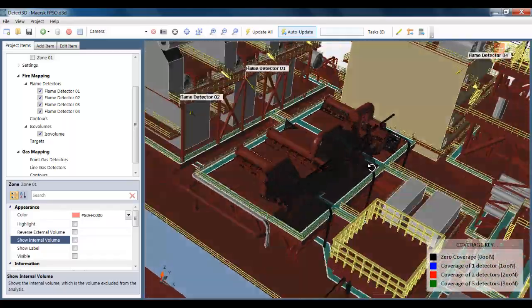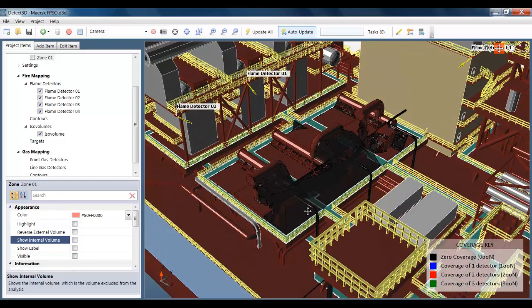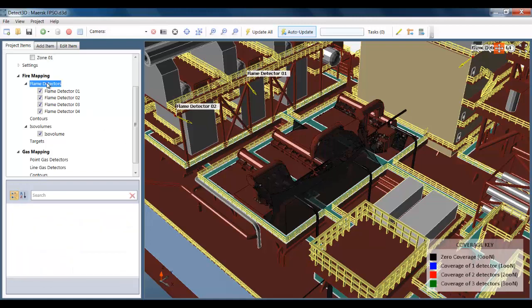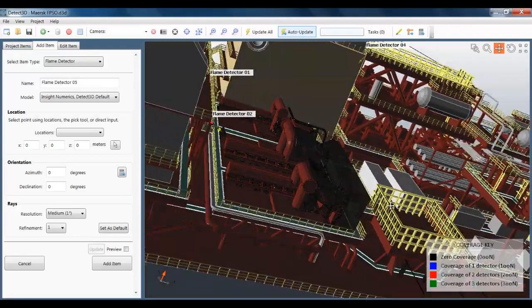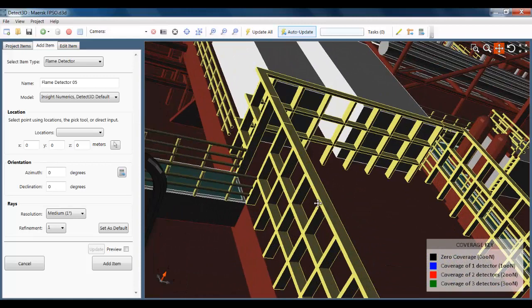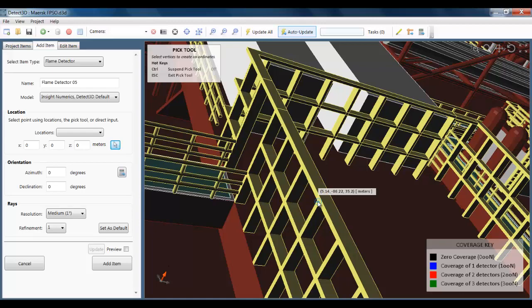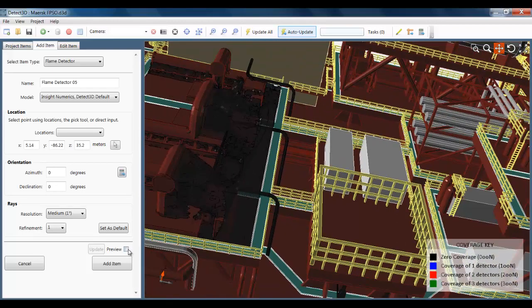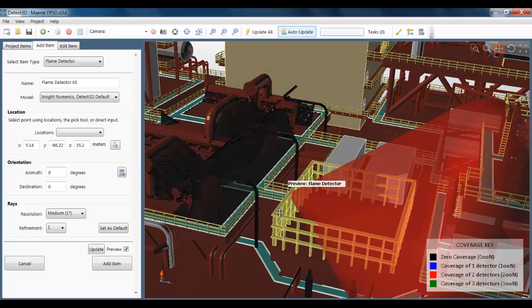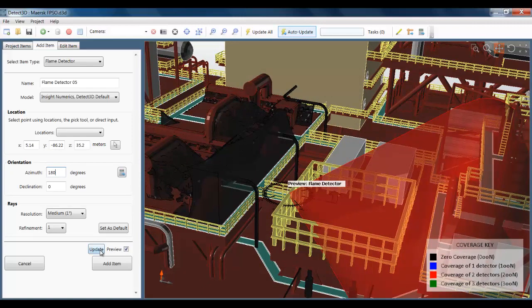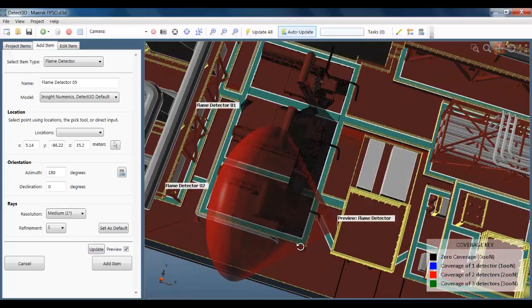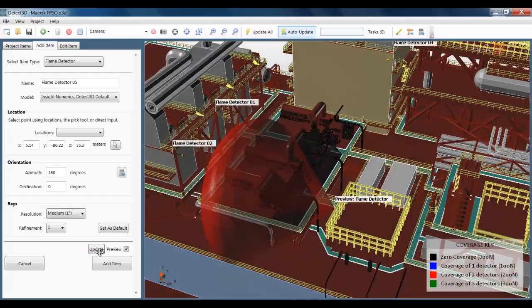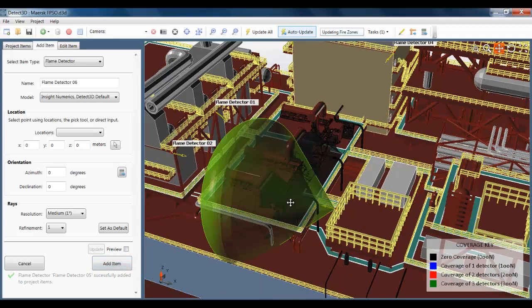We can take a look at the blind spots, and we can see that there are significant blind spots in this area of the fire zone. So I'm going to add a couple more flame detectors here just to try and reduce those blind spots. I've got a little bit of maneuvering to try and get a lock on some likely looking places that you could put a flame detector. I'm just going to lock on these coordinates. And let's have a preview. So it's pointing in completely the wrong direction, so I'm going to have to swivel that round by 180 degrees. That looks good. And as regards the declination, it actually looks at the right level as it is, so we can leave that at zero.